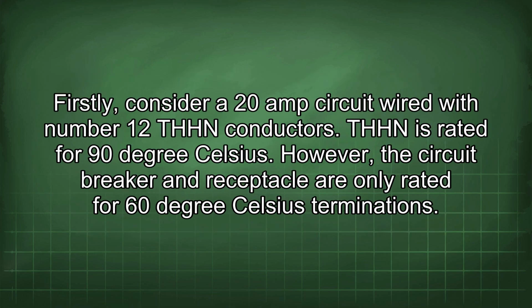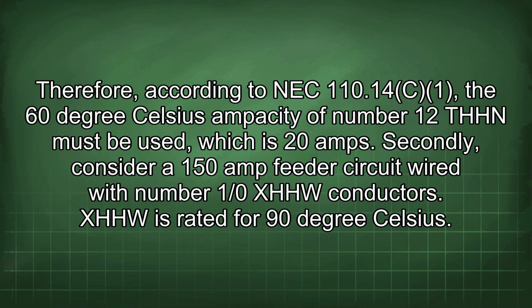Firstly, consider a 20 amp circuit wired with number 12 THHN conductors. THHN is rated for 90 degrees Celsius. However, the circuit breaker and receptacle are only rated for 60 degrees Celsius terminations. Therefore, according to NEC 110.14, the 60 degrees Celsius ampacity of number 12 THHN must be used, which is 20 amps.